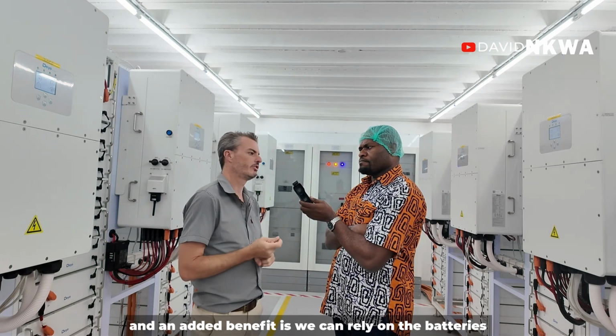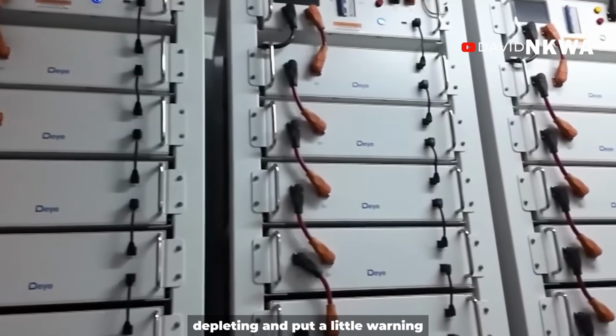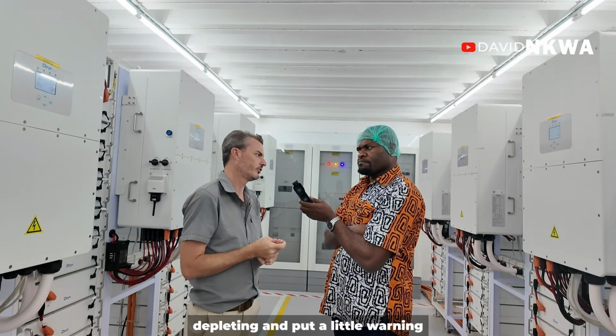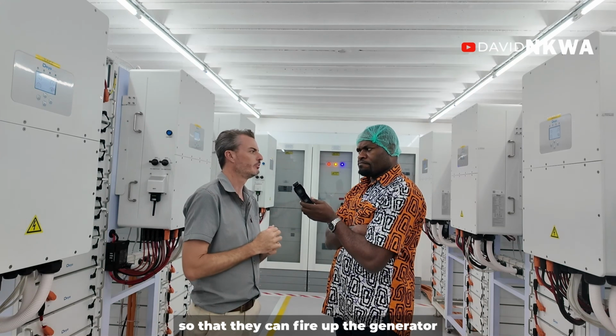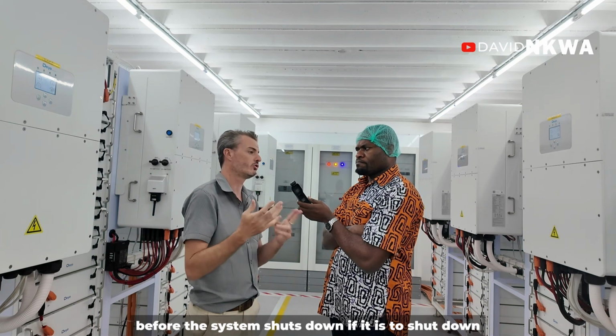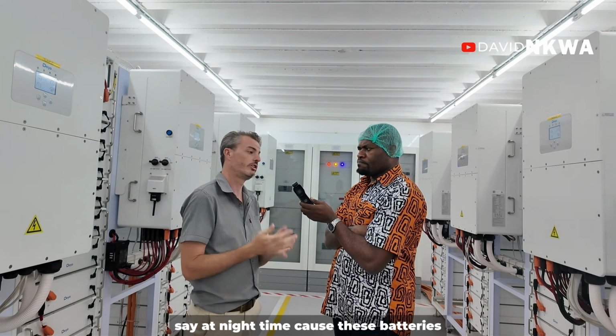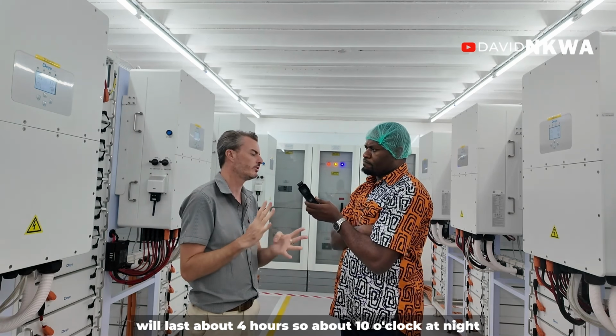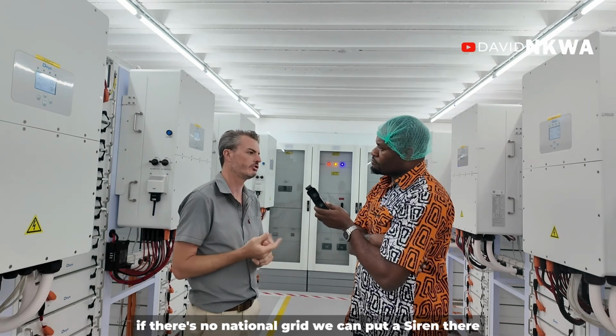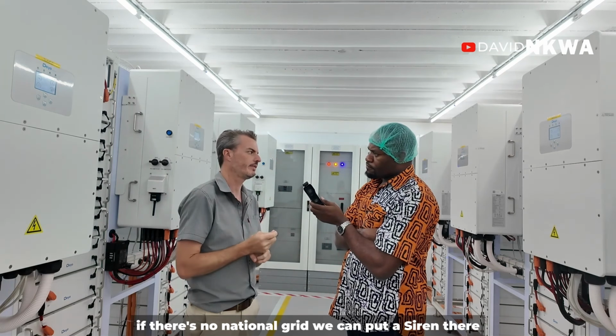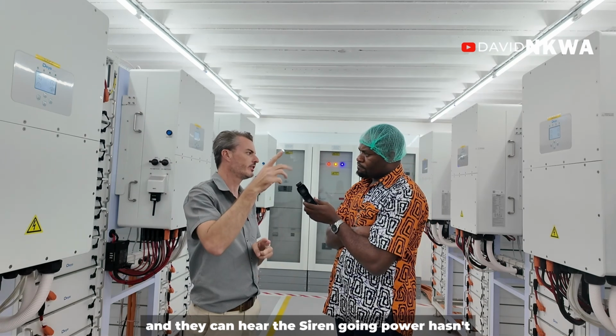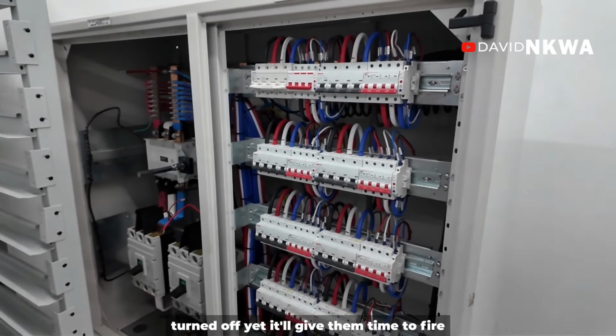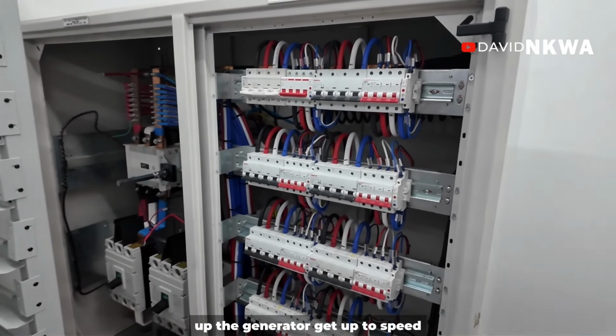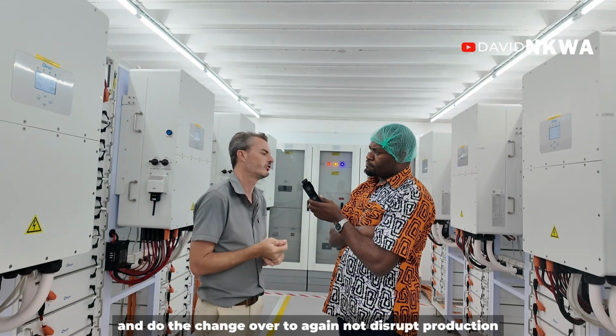An added benefit is we can monitor the batteries depleting and put a warning in place so they can fire up the generator before the system shuts down, say at night. These batteries last about 4 hours, so around 10pm if there's no national grid, we can sound a siren giving them time to fire up the generator, get up to speed, and do the changeover without disrupting production.